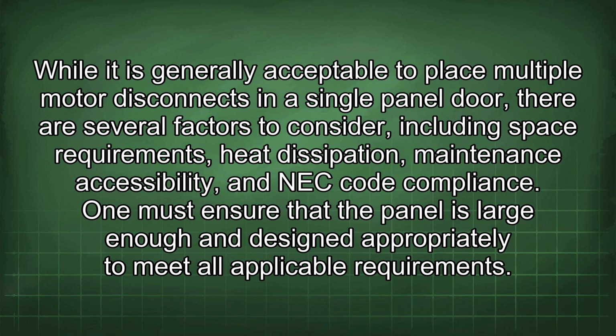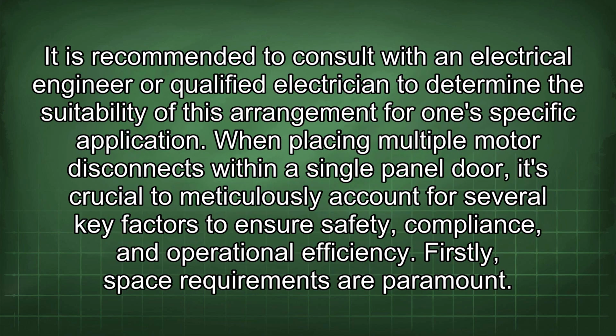While it is generally acceptable to place multiple motor disconnects in a single panel door, there are several factors to consider, including space requirements, heat dissipation, maintenance, accessibility, and NEC code compliance. One must ensure that the panel is large enough and designed appropriately to meet all applicable requirements. It is recommended to consult with an electrical engineer or qualified electrician to determine the suitability of this arrangement for one's specific application.